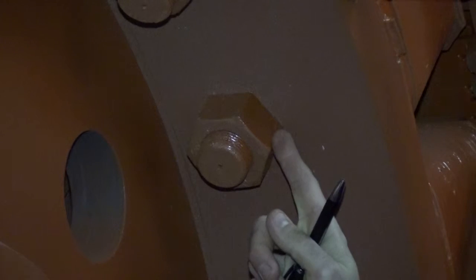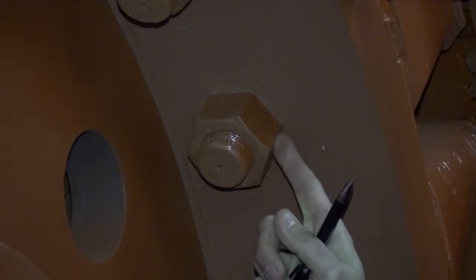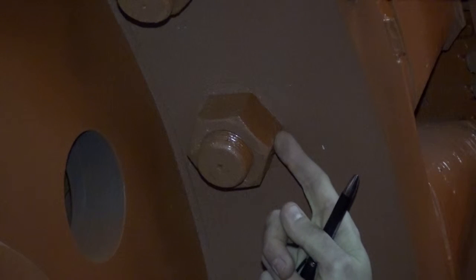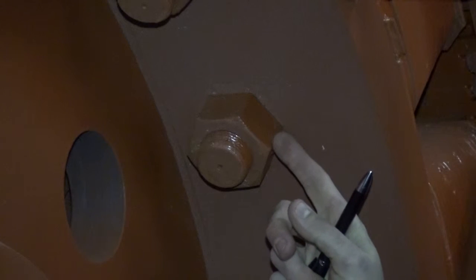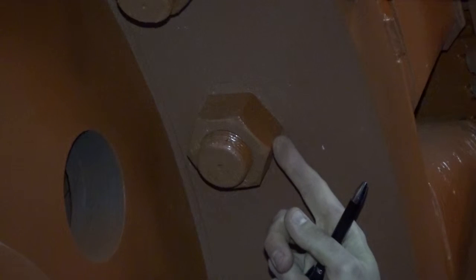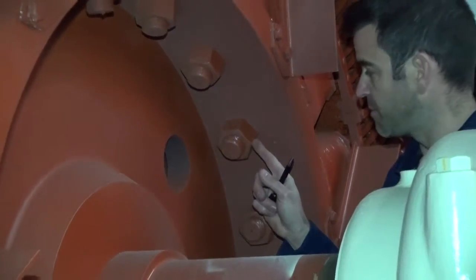These cannot be tightened in the field as they have a very specific torquing specification, but we absolutely want to inspect them for evidence of oxidation or looseness. Inspect every bolt around the assembly on both sides and record any that appear to be damaged or have oxidation.